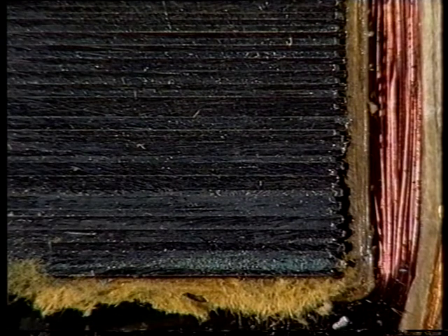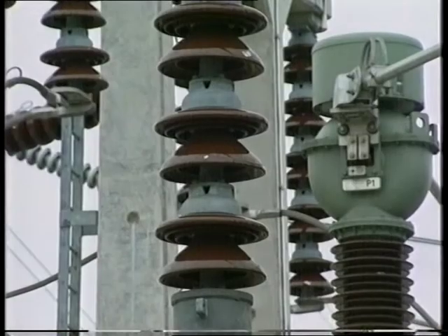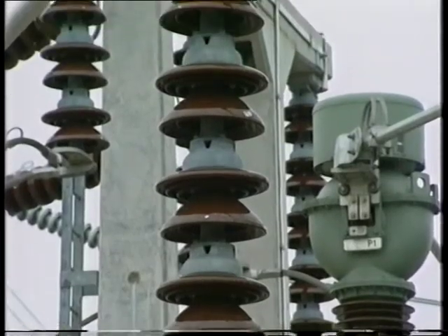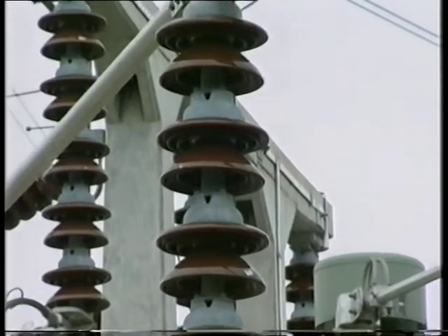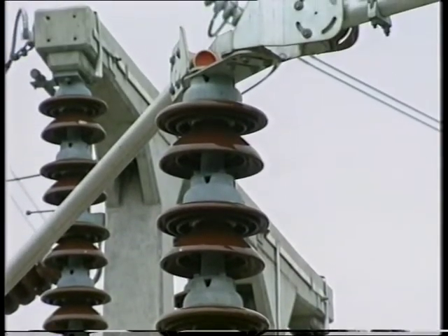The core of both the big transformer and this one are laminated. The alternating magnetic flux in the core tries to induce alternating circular currents within the core. By laminating the core and separating the laminations with an insulating lacquer, the eddy currents are confined to individual laminations and their effect is minimized. Before we leave the substation, look at these porcelain insulators. Why are they made of porcelain? And why are they that shape?